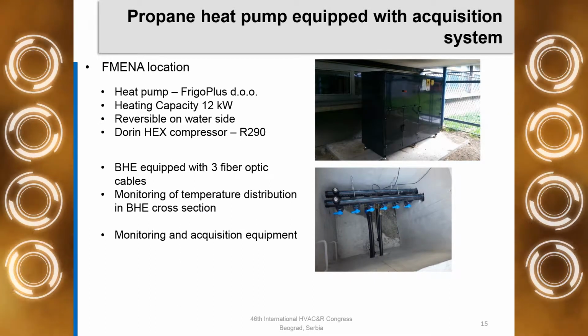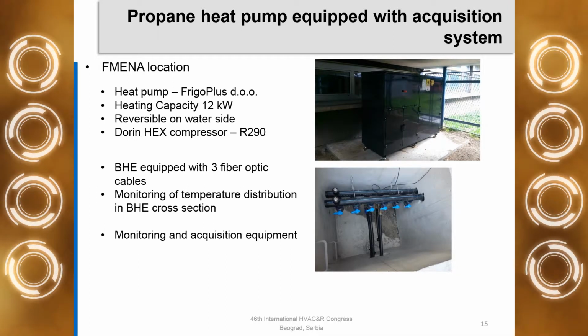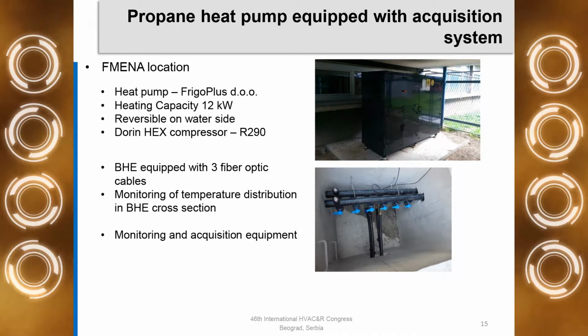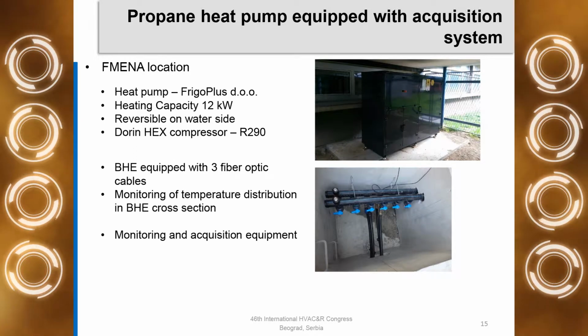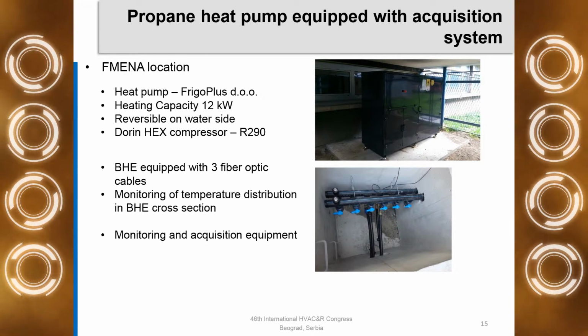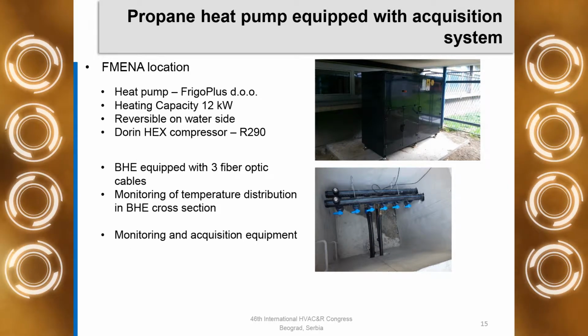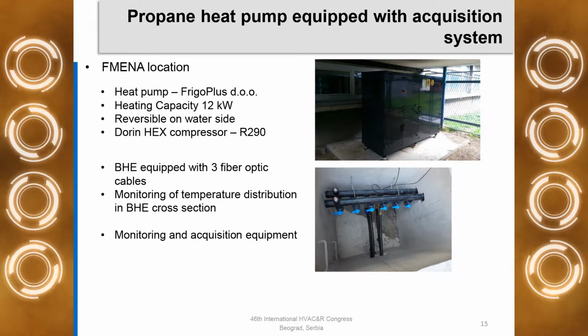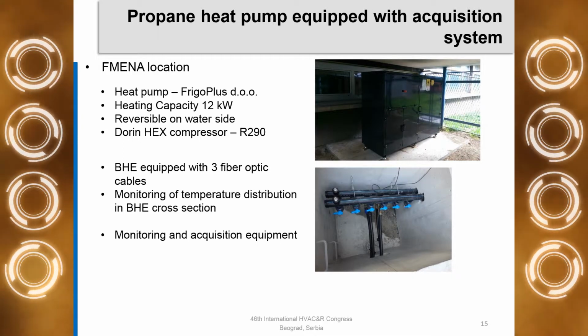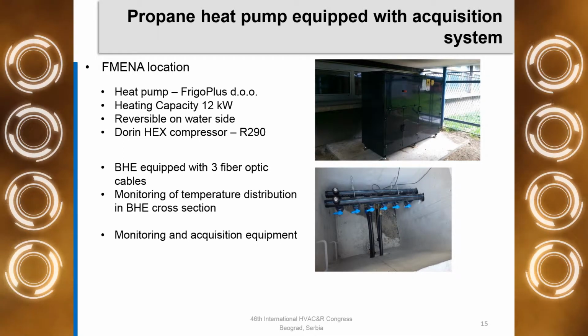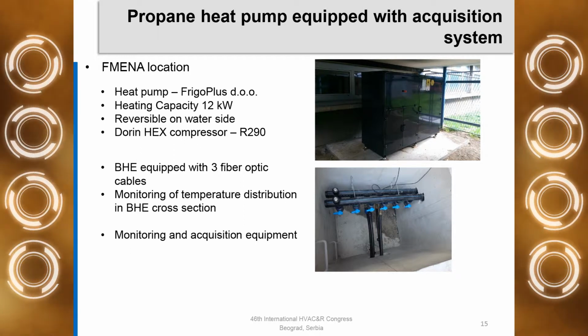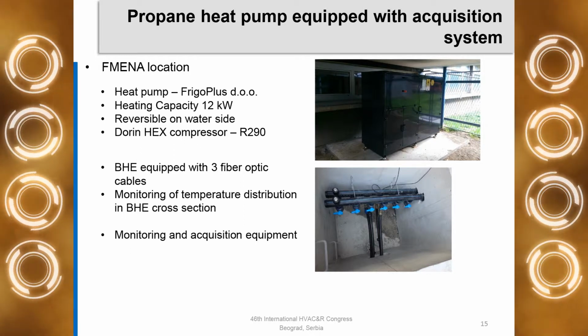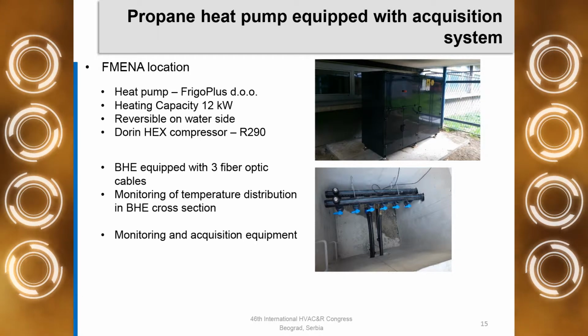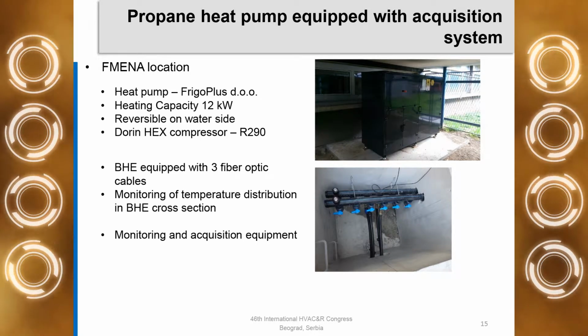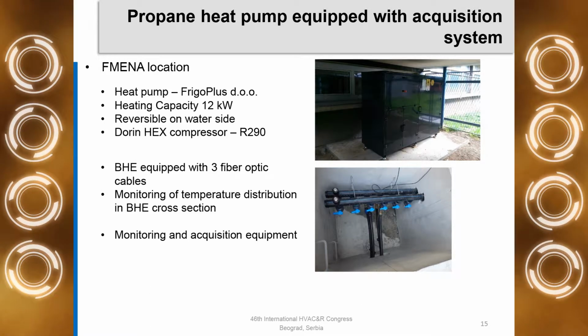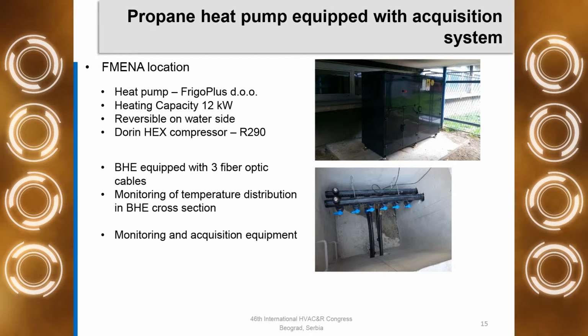On our location, I already said that we have drilled the borehole heat exchanger up to a depth of 130 meters. A propane geothermal heat pump was installed. It is reversible on the water side. That is a slight difference in comparison to those supplied to the high schools. Also, as I already said, the borehole heat exchanger is equipped with 3 fiber optic cables, one placed inside the U-pipe, one placed on the outer surface of the polyethylene pipe, and one placed on the borehole wall. Therefore, we are able to monitor temperature distribution along the depth and along the cross-section of the borehole heat exchanger.